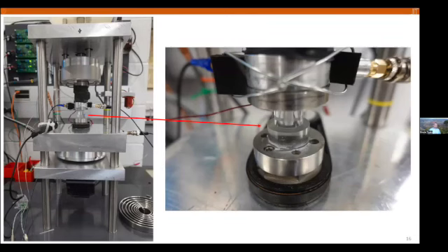Okay, so this is our machine. And our machine is made of an electric motor that winds up a spring, a clock spring, which is very similar to the spring that you see here. We have two of them with different stiffnesses. And the torque generated by this spring is transferred to the bottom sample of these two pair of samples.